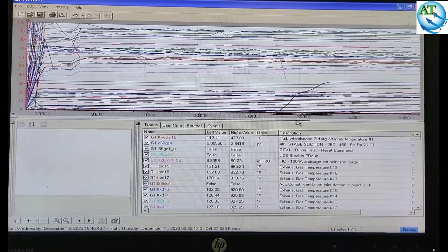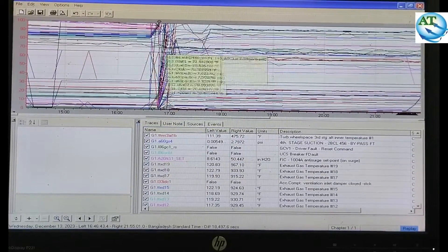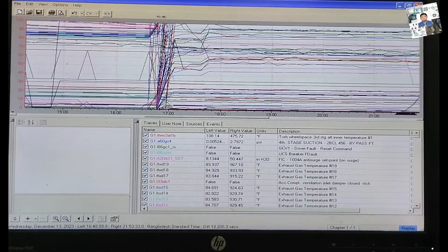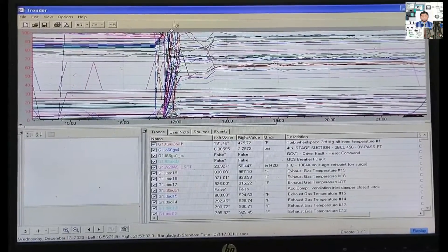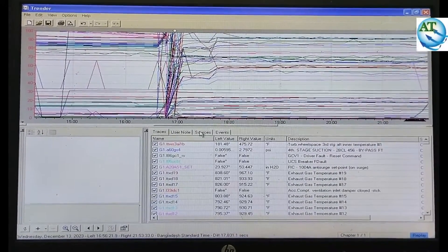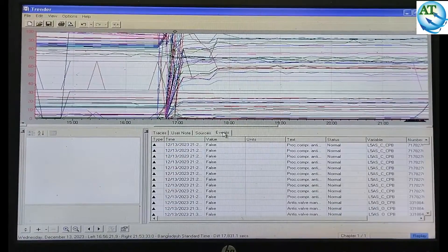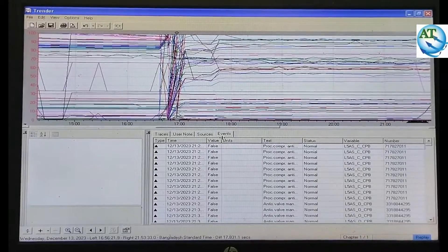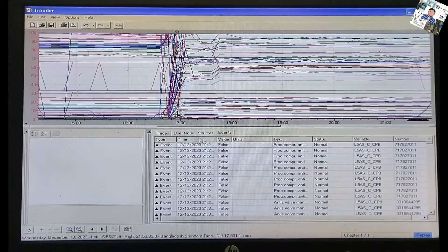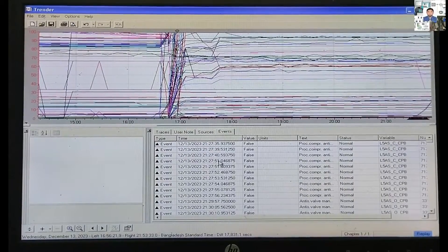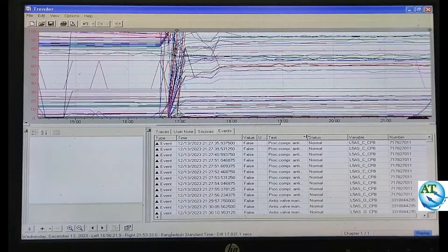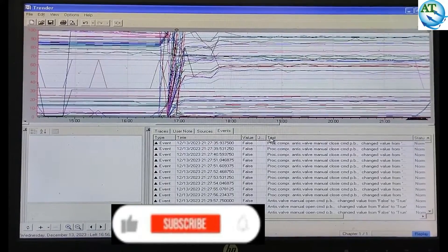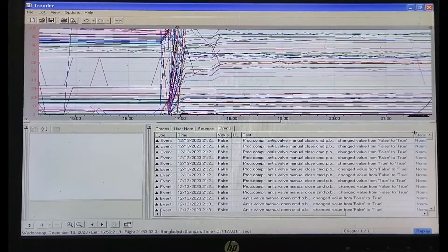Now we zoom out and find out the main cause of the turbine TRIP. You see here the turbine TRIPs and all the trends become abnormal. Left side and right side are normal, but the middle section shows all trends as abnormal — that means at that time the turbine TRIPped. We cannot understand for which reason the turbine TRIPped, so we go to the event logs. In the event logs, you can find out who is the first cause for the turbine TRIP. I am rearranging to see the time, and you can maximize the text to see the root cause.